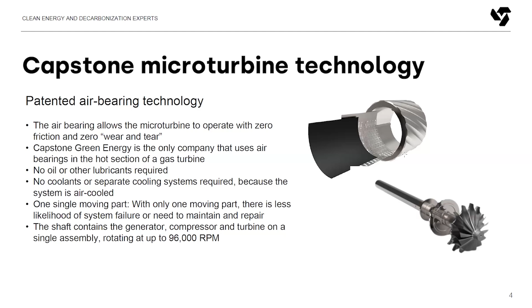For how we handle a lot of our projects, specifically in the biogas space, we like to use a modular approach where we use multiple units to build a larger power system. This has a lot of additional advantages beyond just a conventional CHP project. You can see here in the photo, this system is a C1000, or a 1 megawatt enclosure, but it's got 5 independent 200 kilowatt modules. Each of those modules is capable of operating on its own, so it can run without the other modules. You can shut one down for service while the others continue to operate, and we can stage units on and off as needed to meet the load, including the amount of gas that's available in the case of biogas.